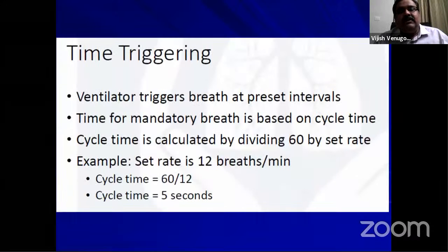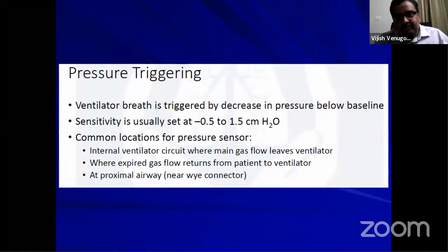Now coming to time triggering, the ventilator triggers breaths at preset intervals. The time for mandatory breaths is based on your cycle time, which comes from the respiratory rate that you have set. So if you have set 12 breaths per minute, the cycle time is 1 minute, which is 60 seconds. So 60 divided by 12, each cycle time is 5 seconds. So the machine will give one breath every 5 seconds. So that is time triggering. Pressure triggering: the ventilator breath is triggered by a decrease in the pressure below baseline. The usual sensitivity we set is minus 0.5 to 2 centimeters of water.